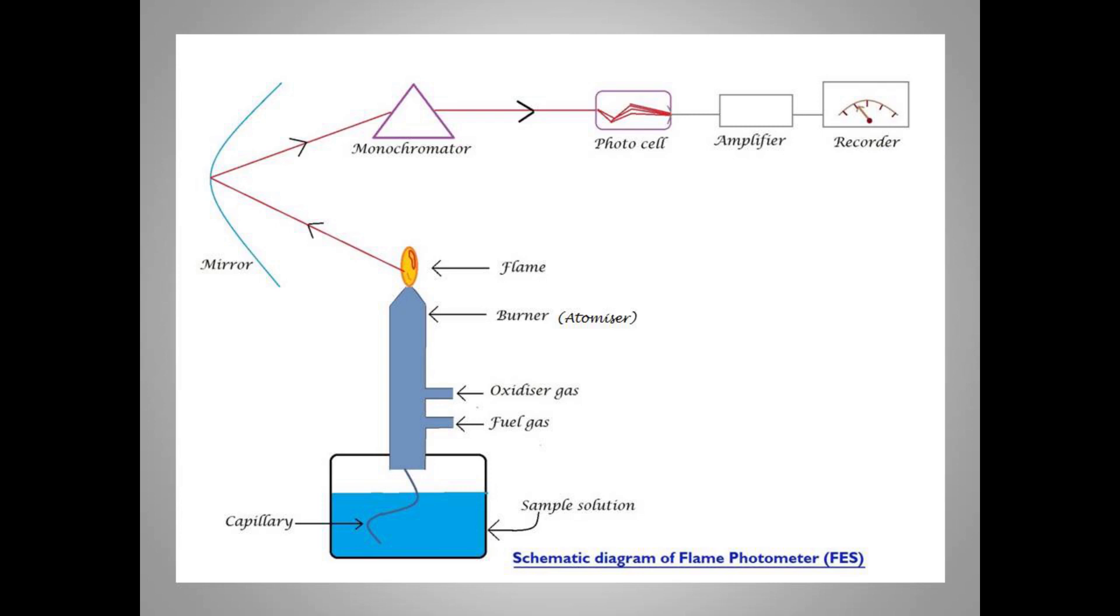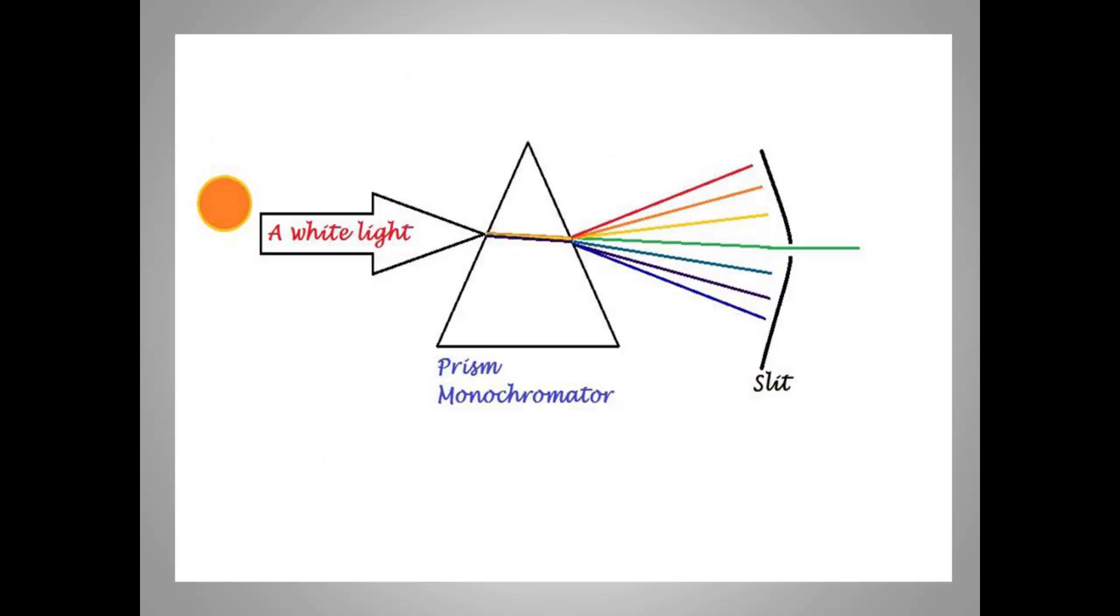Coming back to the instrumentation: In the burner, when the sample gets atomized and starts emitting light, the light falls onto the mirror, which is reflected back to the monochromator. The monochromator is also known as the filter. As seen in the diagram, these monochromators are capable of resolving light into its component, through which they are able to filter unwanted light radiation. Here, in flame emission spectroscopy, the purpose of using filters is to allow only the characteristic radiation coming from the sample and filter off the unwanted light.